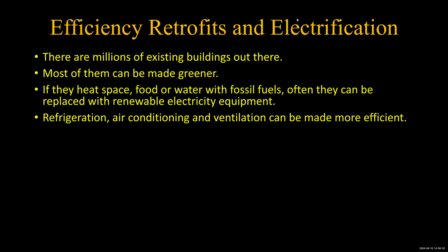Really, it's in BTUs per watt. So if you have a 1 ton unit and you get 12 BTUs per watt, then to get those 12,000 BTUs is going to take 1,000 watts. That's the definition of the Seasonal Energy Efficiency Ratio. The units are BTUs per watt.